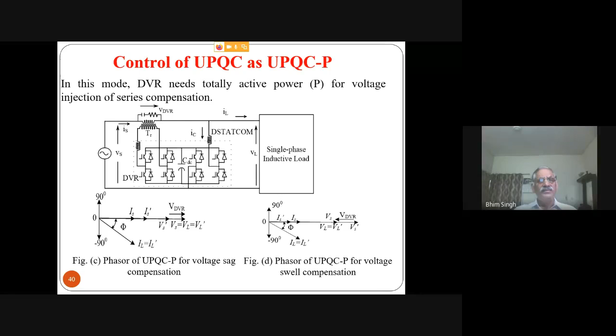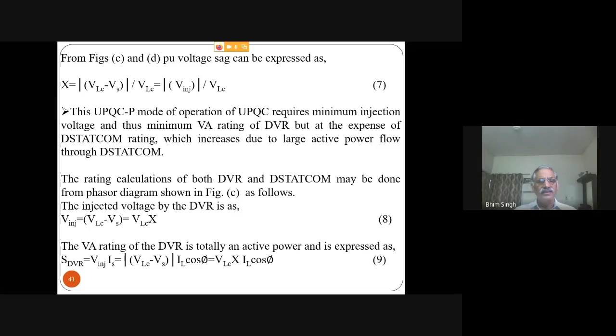These are all calculations of rating estimation: what should be the series injection voltage, the voltage rating of the series injection, the current rating, the calculation of the shunt compensator rating, the series compensator rating, and the overall compensator current rating like DStatCom. It's not the same way we do it for DStatCom alone, because the series compensator really affects the rating of the shunt compensator, and the shunt compensator also affects the rating of the series compensator.